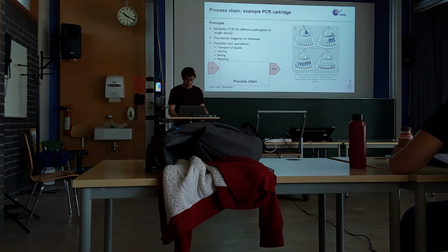And by having this waste structure here at the bottom and defined volumes for each of these cavities, you will end up with the same liquid volume in each of the reaction chambers, which is important for a comparison between the chambers. And then in the last step, you accelerate, and the liquid gets transported into the final reaction chambers, where you can then do the readout by doing a PCR, for example.